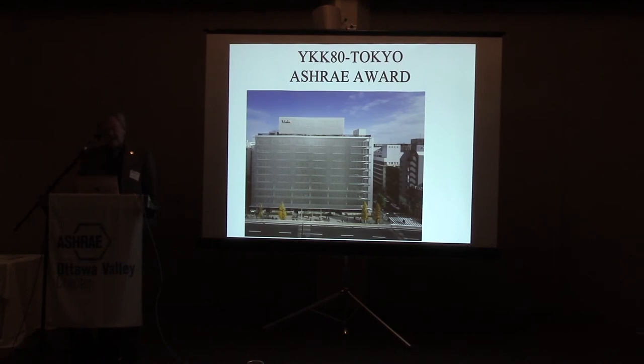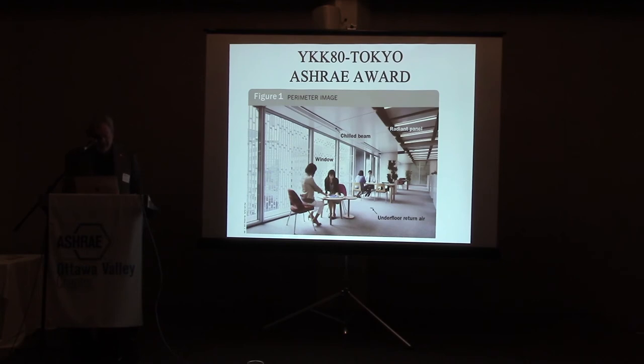Here's one building which last year won the ASHRAE award. It has radiant heating and cooling, most of the time cooling because of internal loads. The principle here is a radiant panel in most of the office, but at the perimeter, where you may have some higher load from sunshine, they combine it with a chilled beam. The chilled beam is basically a fan coil that you put up in the ceiling. The advantage is that the water temperature you need for the radiant panel and the chilled beam is basically the same, so you can run it with the same water temperature.